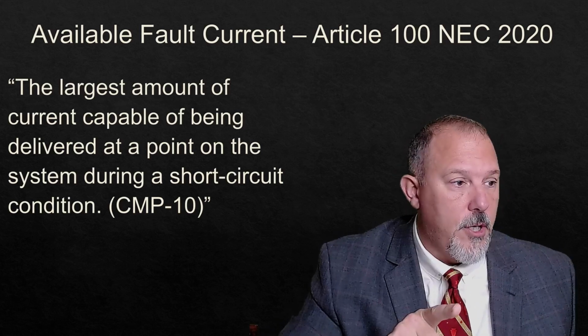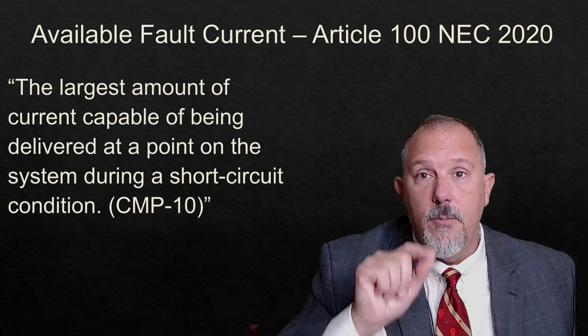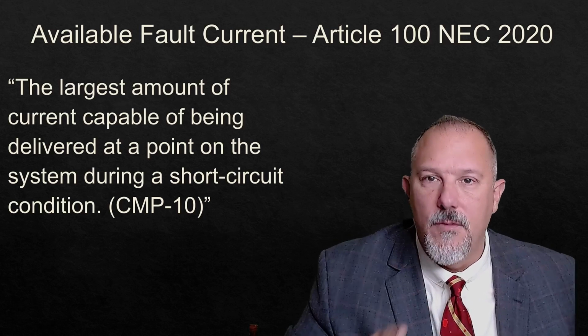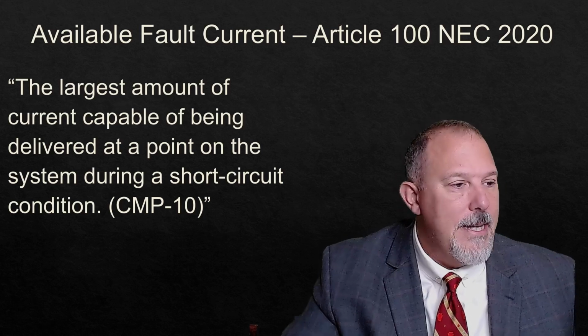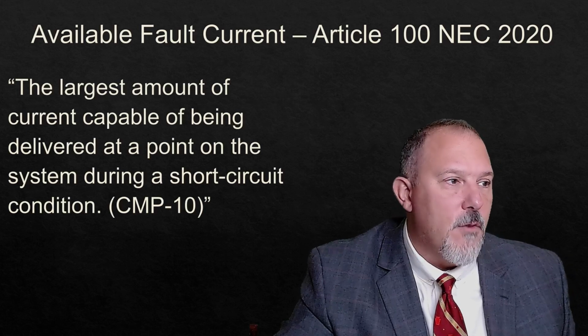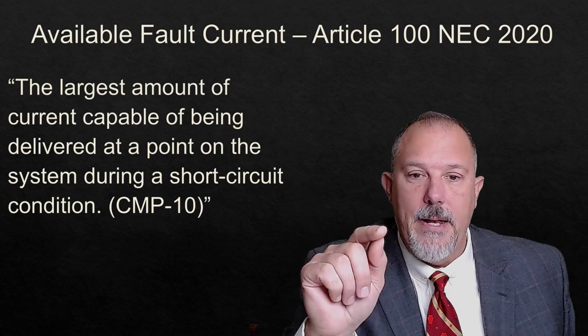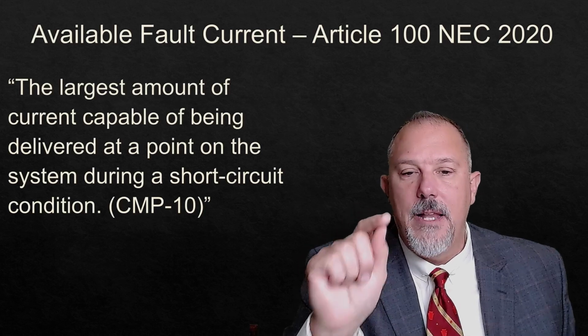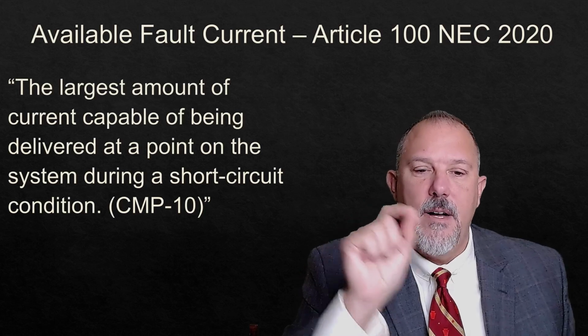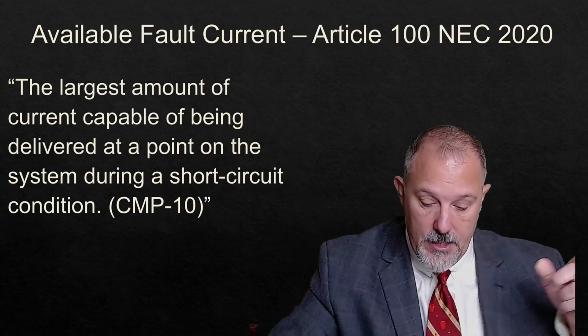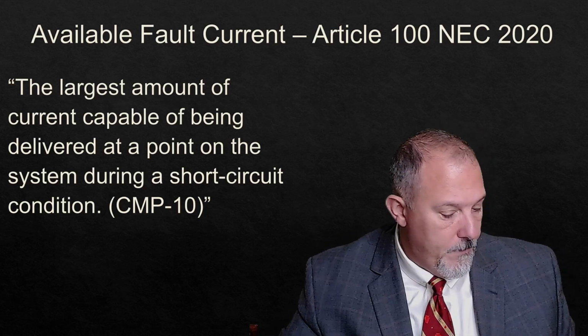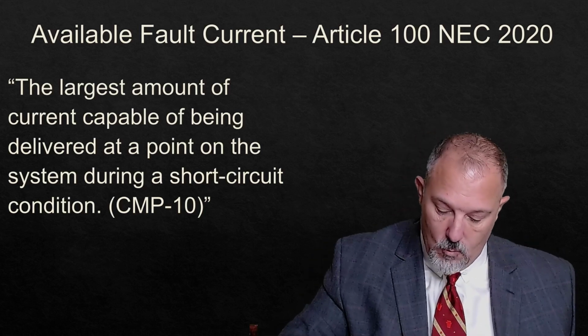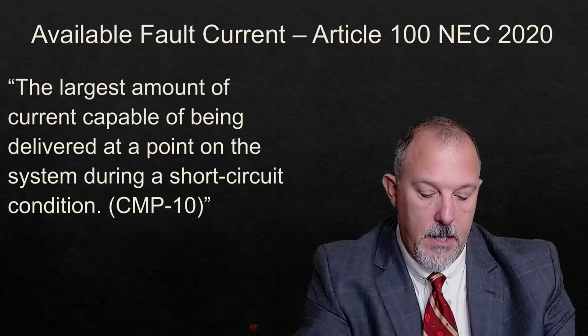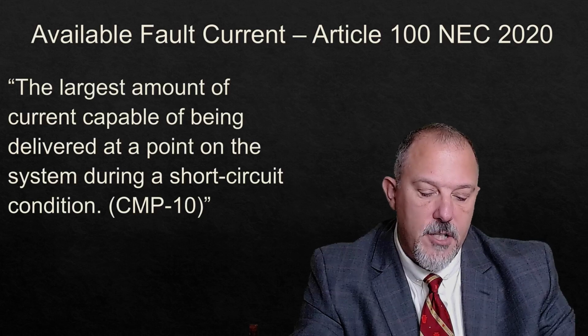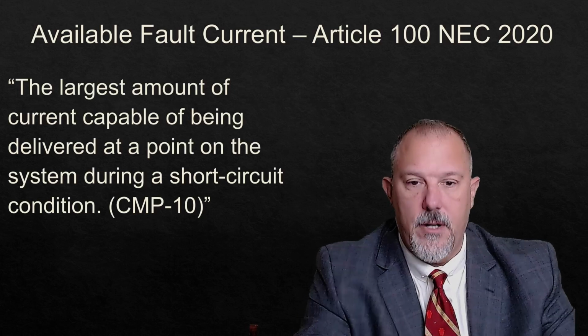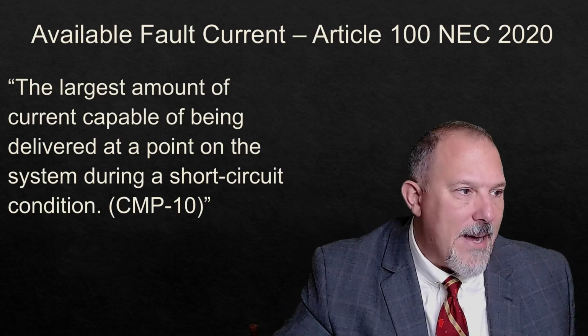So 110.24 in the National Electrical Code is directly related to available fault current. Why? How do we know that? What's the title of 110.24? Available fault current. Now, what it says: available fault current marking, service equipment at other than dwelling units shall be legibly marked in the field with the maximum available fault current. That's in the 17 code. Let's take a look at 110.24 in the 2020 code. 110.24 says service equipment at other than dwelling units shall be legibly marked in the field with the available fault current. So they got rid of the word maximum from 110.24.